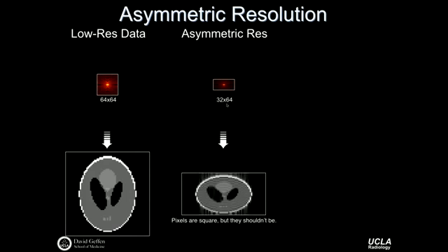If I acquire half of the Fourier data, I can do that in about half the time, because I don't need as many phase encode steps. So I didn't go as far out in K-space for, say, this acquisition here, and I only have 32 KY encode points, and I still have 64, say, in the left-right direction.